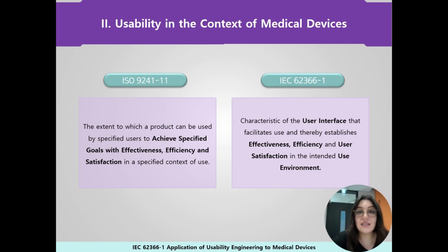Going on to the IEC 62366-1, which we just saw in the slide before this one, usability is defined as a characteristic of the user interface that facilitates use and thereby establishes effectiveness, efficiency, and user satisfaction in the intended use environment. So we have another important element here, which is the user interface, also abbreviated as UI. The user interface is basically all means by which the user and the medical device interact with each other.